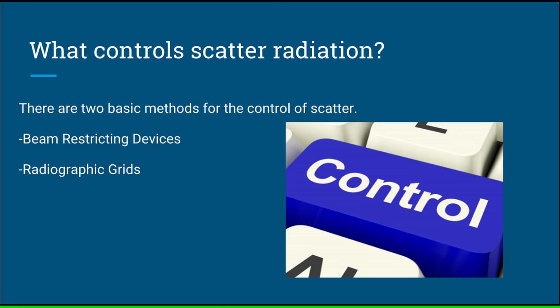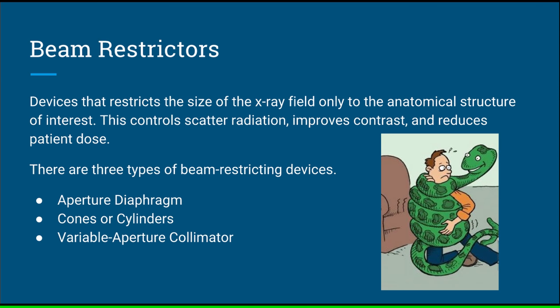What controls scatter radiation? There are two basic methods for the control of scatter: beam restricting devices and radiographic grids. Beam restrictors are devices that restrict the size of the x-ray field only to the anatomical structure of interest. This controls scatter radiation, improves contrast, and can reduce the patient dose. There are three types of beam restricting devices: aperture diaphragm, cones or cylinders, and the variable aperture collimator.